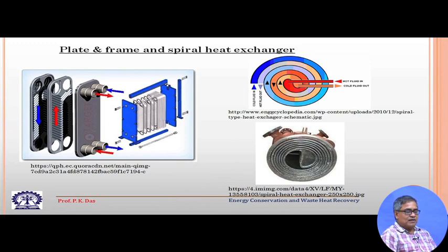There are certain limitations, like these heat exchangers cannot withstand very high pressure because there could be leakage from the gaskets, or very high temperature either. And it is suitable for handling cleaner fluid, because the passages are very small, they can get clogged by dirt, etcetera, if the fluid carries that. So, apart from this, this is a very good arrangement for intense heat transfer between two streams, suitable for waste heat recovery purposes, where heat is to be extracted from a hot fluid by another fluid, particularly when there is power generation.